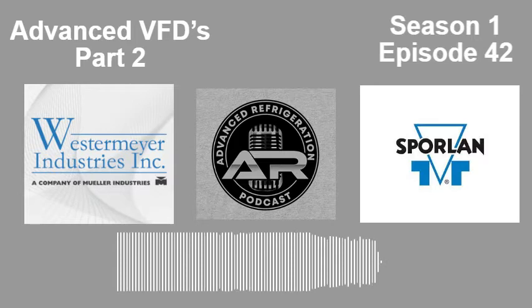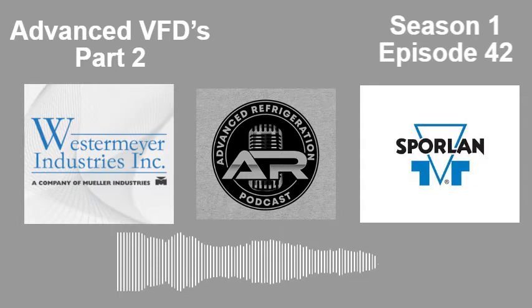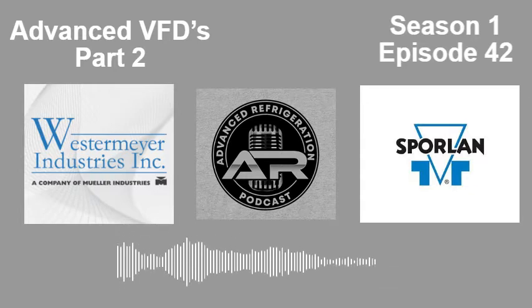Well, one of the things I was taught is, any kind of contactor, if you contact Eaton or whatever, they're going to tell you that their contactors are made to not exceed, some manufacturers are different, anywhere from 6 to 10 cycles an hour, because of that. Your thoughts? You agree?